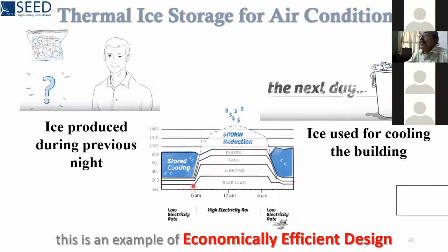In normal condition, your demand may go up to something like 1400 kilowatt. But if you use the stored cooling in ice, it will come down to 800. That means there is a saving of 600 kilowatt reduction. So this is an economically efficient design. I'm not saying it is an energy efficient design because energy is already used to produce the ice. So there is no saving in energy, but you are producing the ice at a lower cost. So economically you are saved. So it is an economically efficient design.